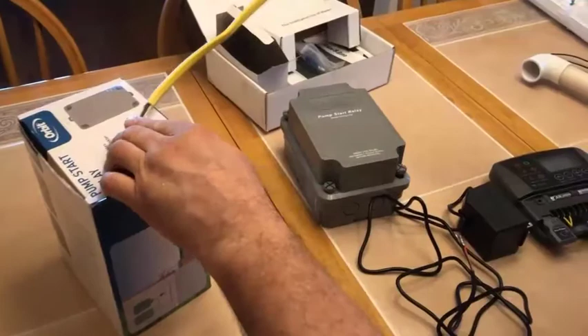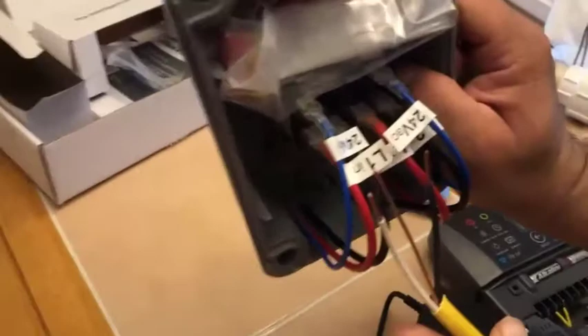So what happens is this comes from your breaker box to your pump start relay. As I described in my prior video, the pump start relay has line in versus line out. Let me get this open a moment. So these, the black and white, are going to be your line in 1 and line in 2. These are your ins.